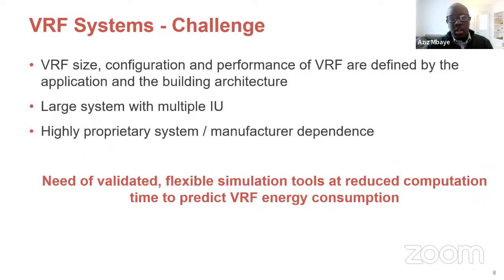And from this description, it is clear that unlike traditional heat pumps, a VRF configuration is unique to the building architecture, which ultimately impacts the size, the performance, and the operation of the system. Also, VRF can include up to 100 indoor units, which will add more complexity to the design and the operation of the building HVAC system.